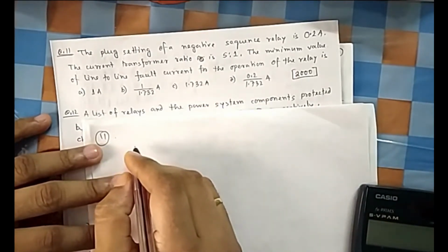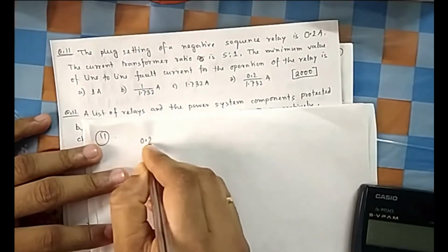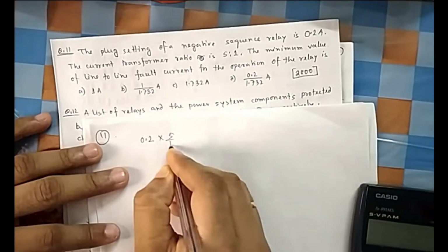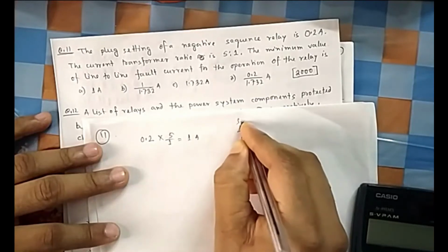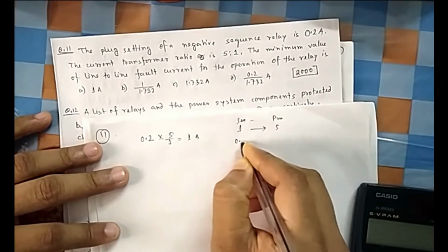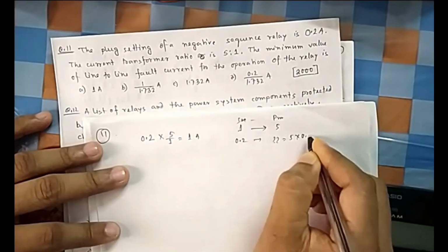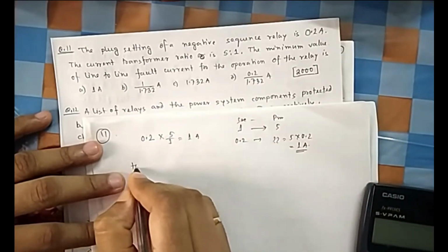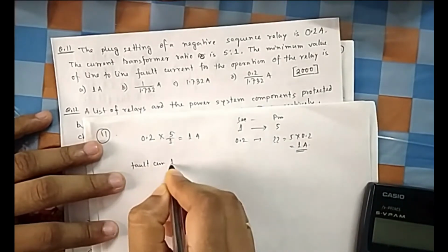So what will be the minimum fault current in the primary side for which it will trip? 0.2 is in the secondary. So in the primary it will be 5/1. That means you can think of it this way: if secondary is 1 ampere, then primary is 5 ampere. If secondary is 0.2, then primary will be how much? Normal unitary method, 5 into 0.2, that is 1 ampere.